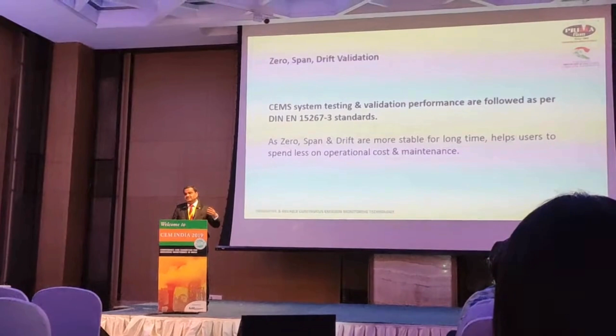To validate or test the performance of this technology, we follow zero span drift validation, which is the most important test to do at the site. We follow standards like 15267. In the first 6 months, we studied the entire standard, formulated it into an Excel sheet considering all the formulas, got virtual results, and then converted the entire thing into software.